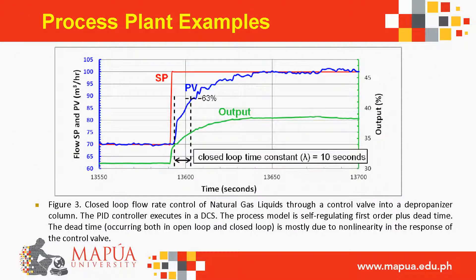Process plant example: closed-loop flow rate control of natural gas liquids through a control valve into a depropanizer column. The PID controller executes in a DCS. The process model is self-regulating first-order plus dead time; the dead time in both open and closed loop is mostly due to nonlinearity in the control valve response.